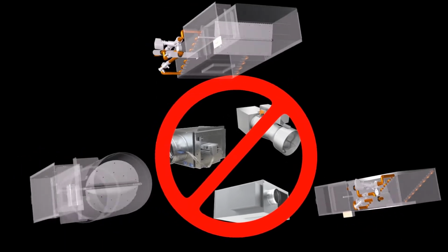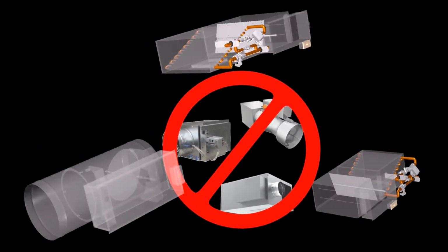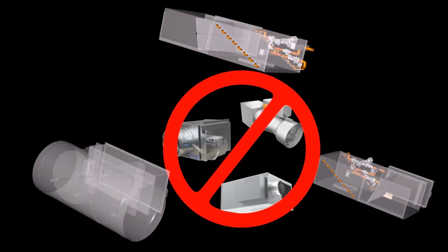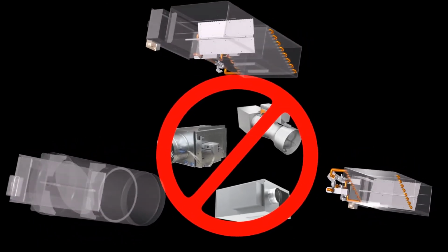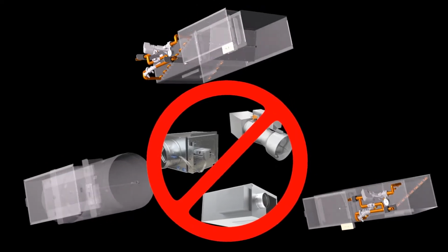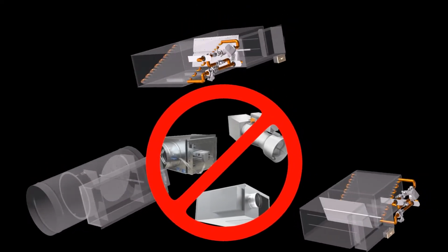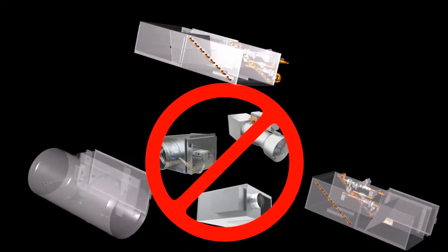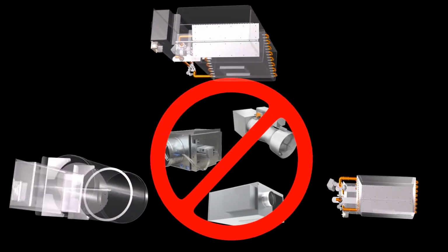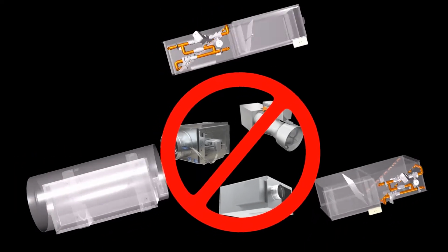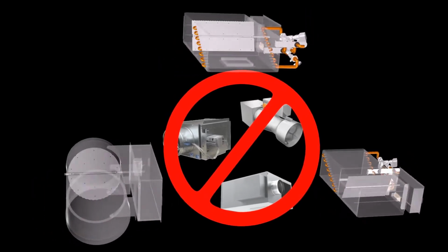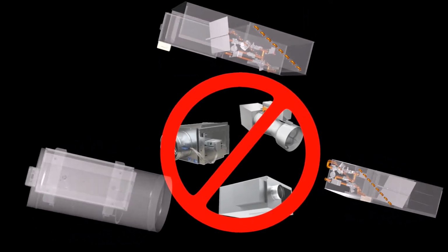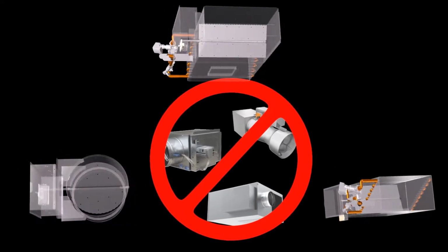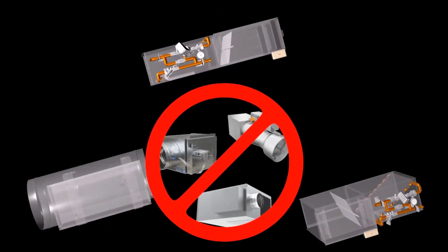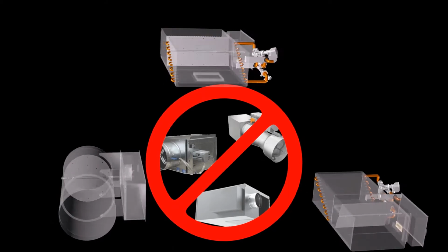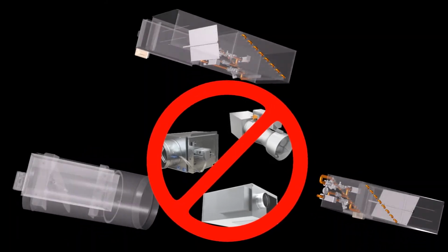The SAV is the most economical way to measure and control low airflows over a wide dynamic range with a single-size self-balancing intelligent air terminal device. Using patented variable orifice plate technology, featuring up to a 100-to-1 turndown with up to plus or minus 3% airflow accuracies. The SAV is so accurate, it can measure its own low damper leakage at 100% closed. Available in round and low-profile rectangular body styles, including custom variable aspect dimensions.